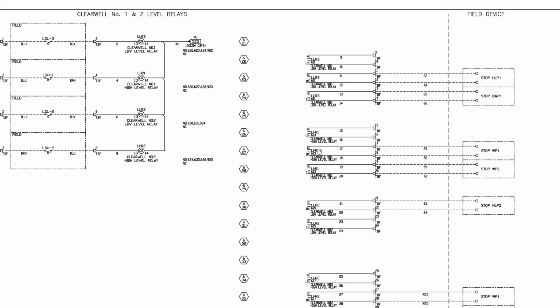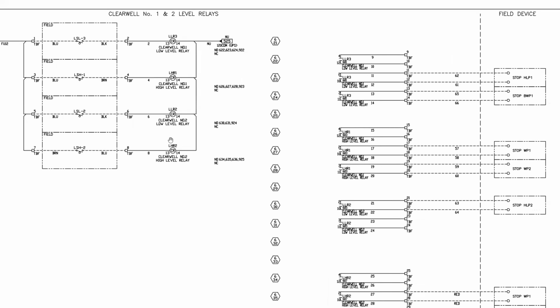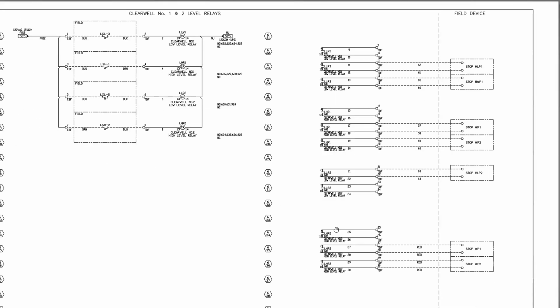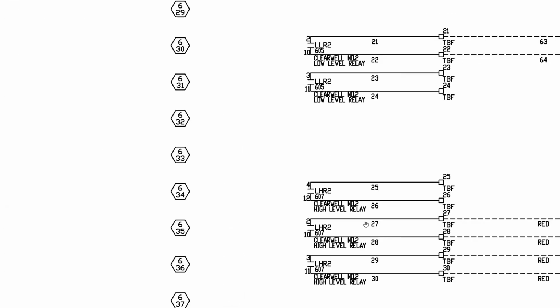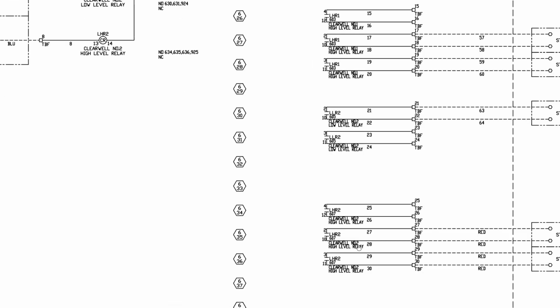These would be these high level switches. So these reservoir clear well switches, when they're high, they will force stop the well pumps. So the well pumps can't run if the reservoir is too high based on these level switches. And these well pumps also can't run when clear well level 2 is too high.